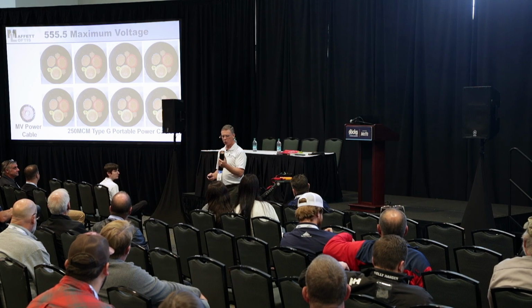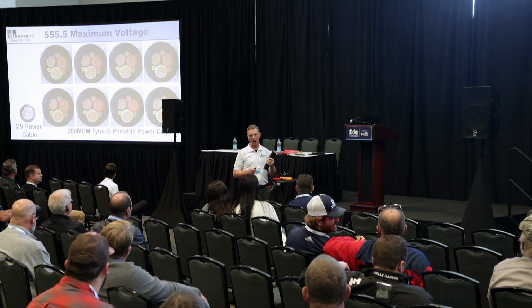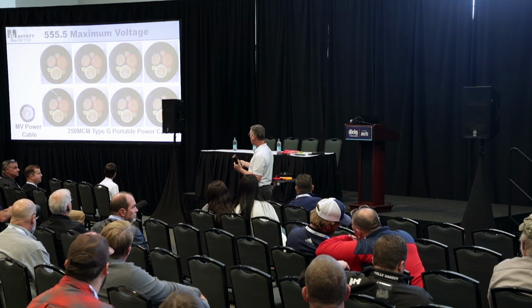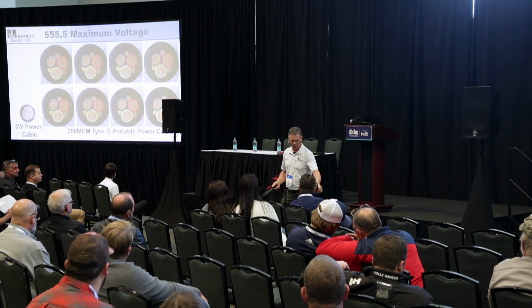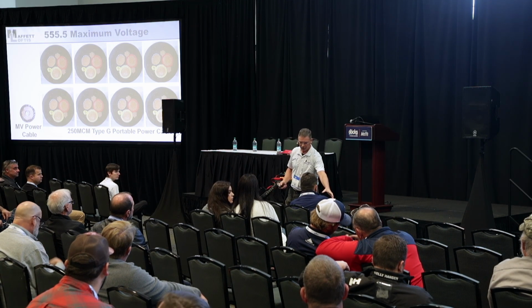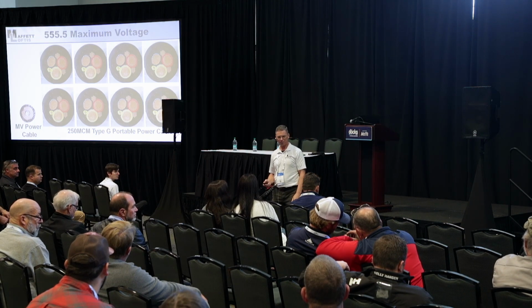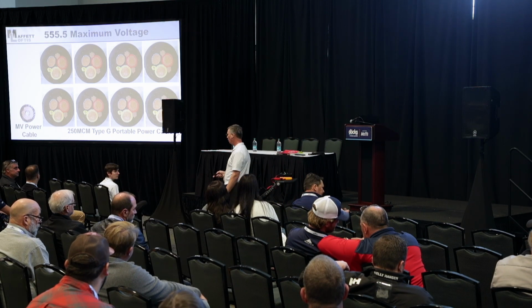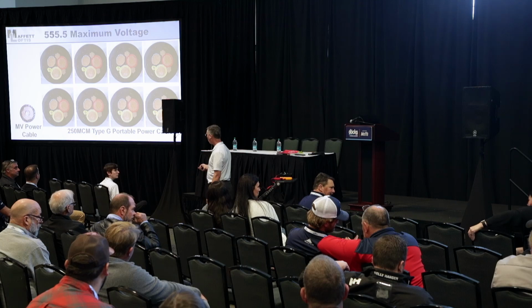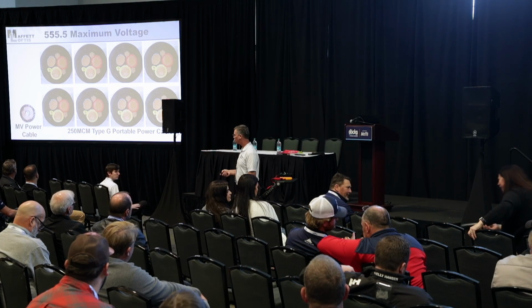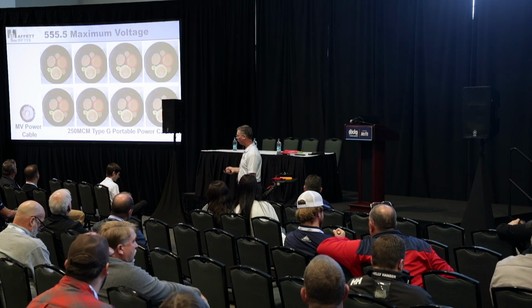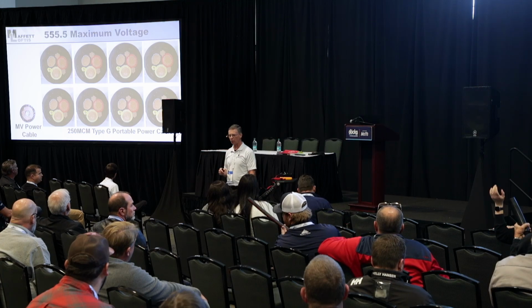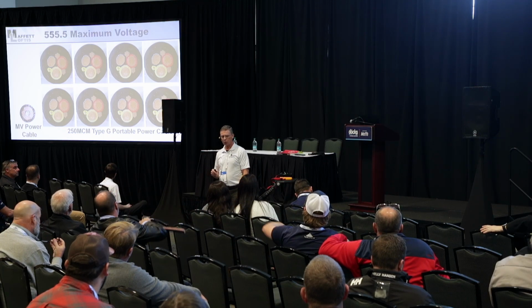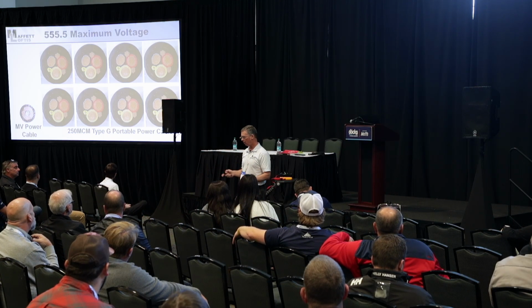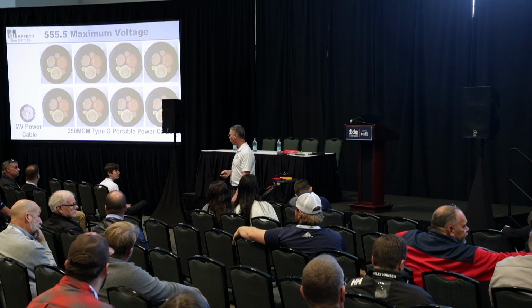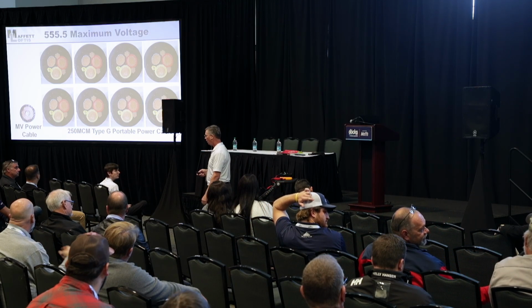So the advantage of using that one wire versus all this other portable power cable, I'll pass this around too, feel how heavy it is. That's a 250 MCM portable power cable. So that one medium voltage cable can carry the same amount of power as all this other cable, and that's at 480 3-phase, by the way. It's a massive amount of power you can put through that one medium voltage cable.